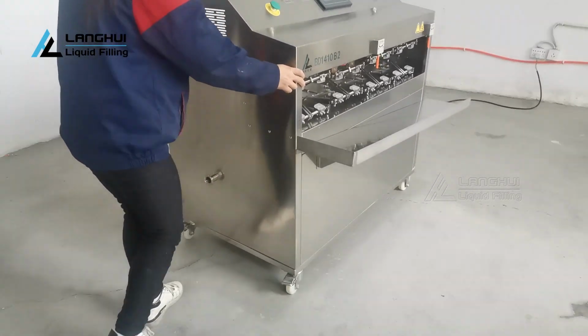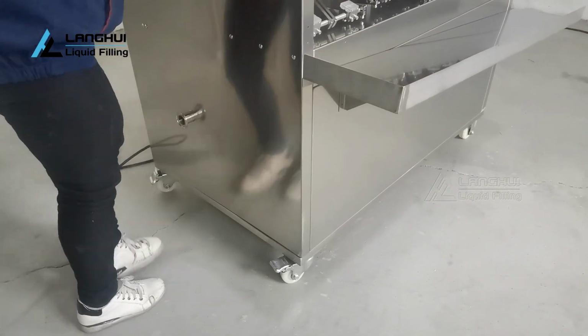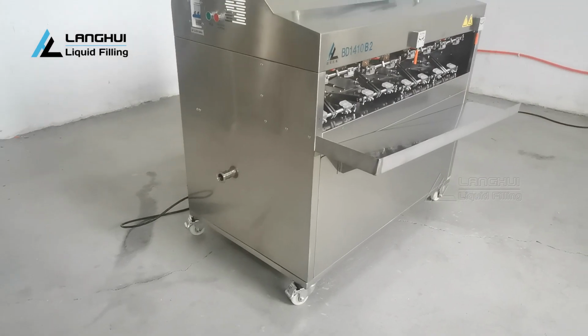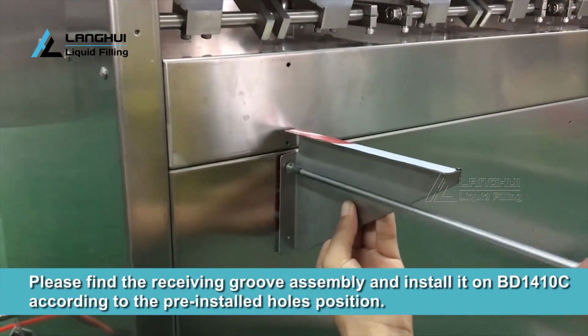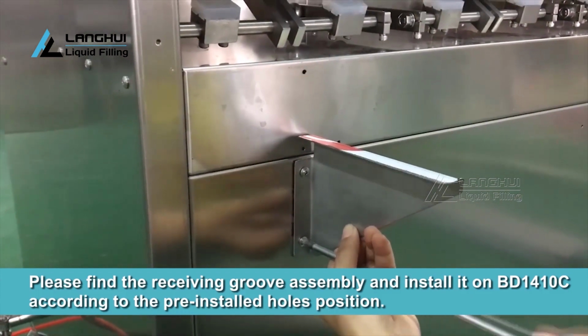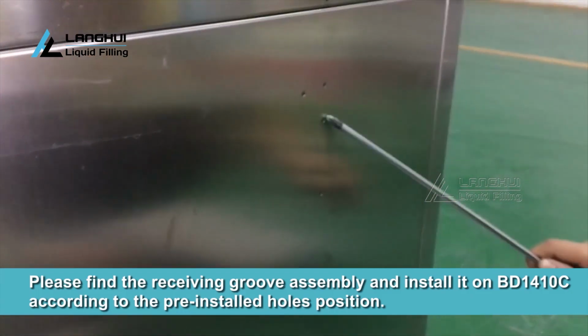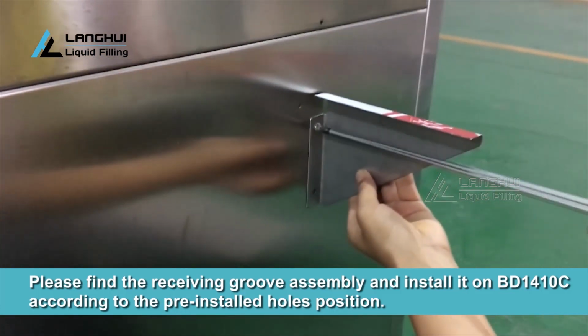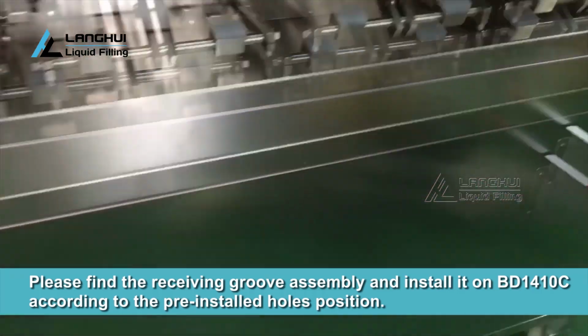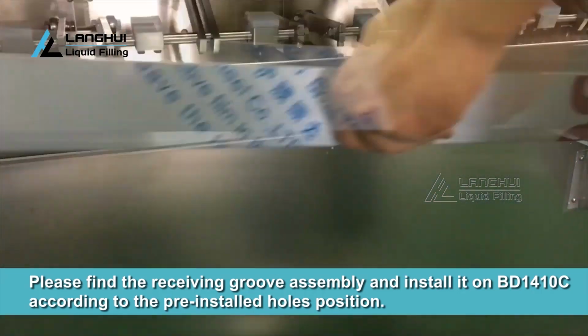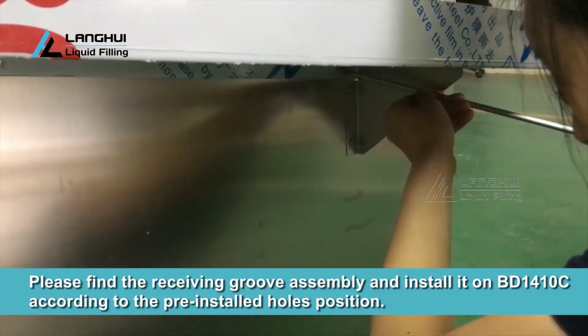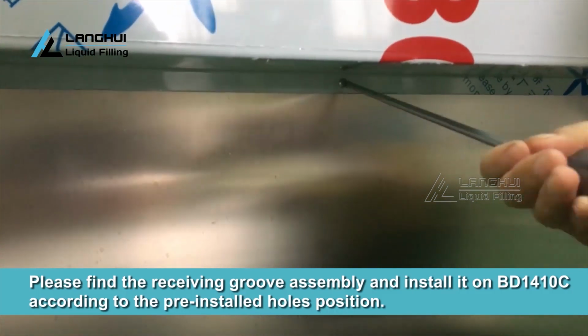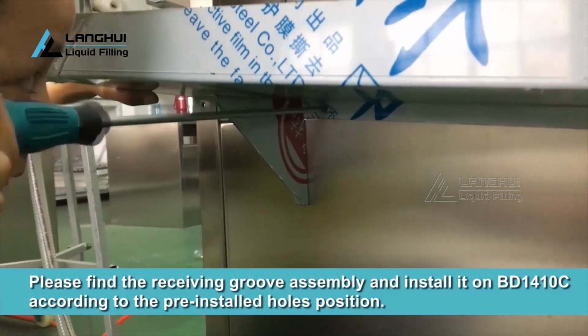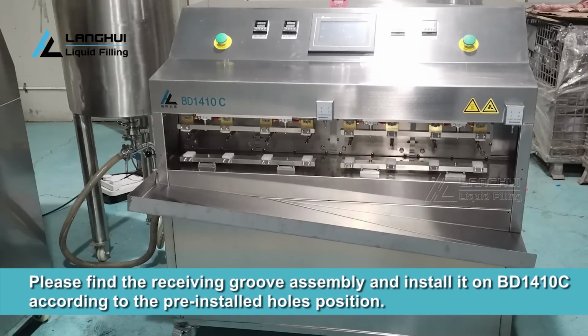After confirming the position of the machine, please lock both end casters. Please find the receiving groove assembly and install it on the machine according to the pre-installed hole positions. It must have a good ground wire connection. Please check the standards of the local electricity supply grid.